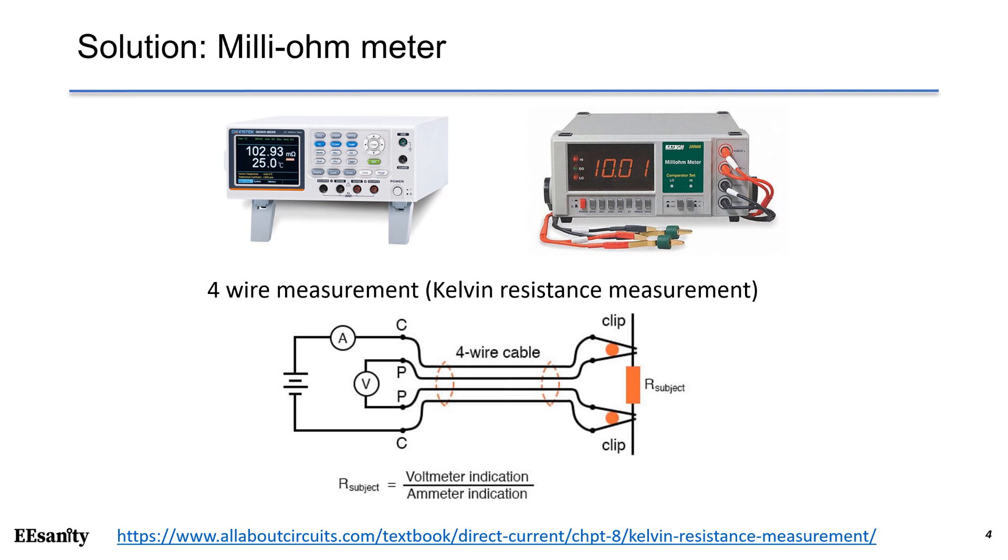The most convenient solution is to use a milli-ohm meter. It has four wire Kelvin connection. One pair of wire provides a current to flow through the resistor under test. Another pair to measure the voltage drop across the resistor. As a result, the measured resistance equals to the voltage measurement divided by the current measurement.